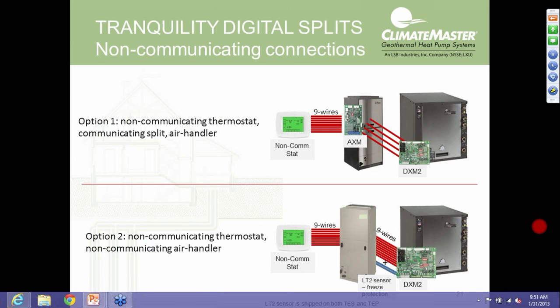Now, if for whatever reason you wanted to use a non-communicating stat, Honeywell, whatever your flavor is, you can still do communication between the air handler and the compressor section, the TES, and then use non-communication between that AXM board and your thermostat. So that's showing a single thermostat here. You could also do duct zoning the same way through the conventional wire inputs.